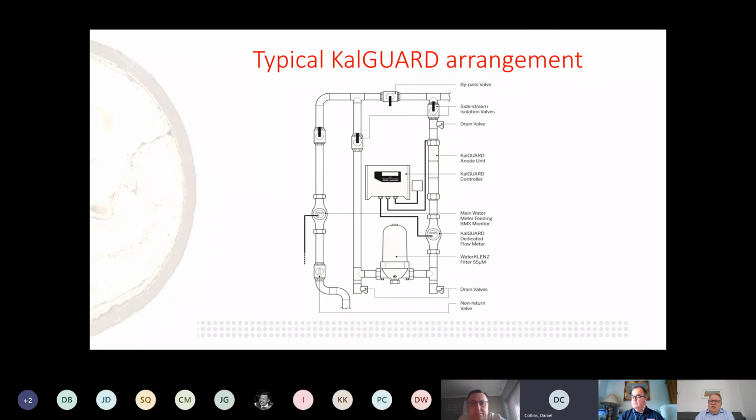Just a quick one on that. Maybe what we could do for illustration would just be to move the isolation valve as far left or right as we can, depending on which side the incoming supply is on. I assume the left. So if we move the isolation valve as far over to the left to the T as we can, then you're reducing that dead leg as much as possible. Paul is obviously correct with the water authorities not liking dead legs, but like you say, as long as they're flushed and as long as that valve is as close as possible to the incoming supply, then there's little to no risk really.